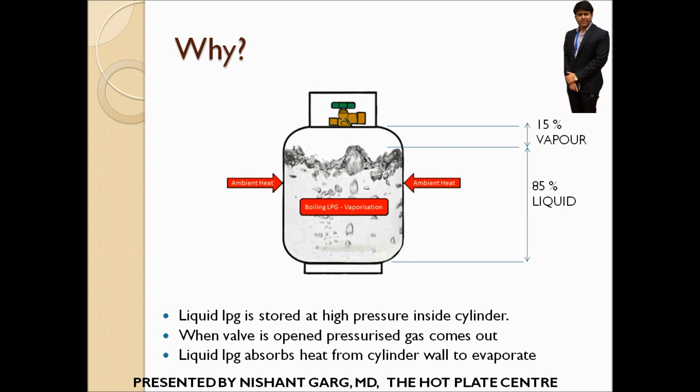To compensate for this heat loss, the cylinder takes heat from the ambient atmosphere. Now if this rate of heat extraction is very high, or the liquid LPG being extracted from the cylinder is very high, the cylinder is going to freeze.